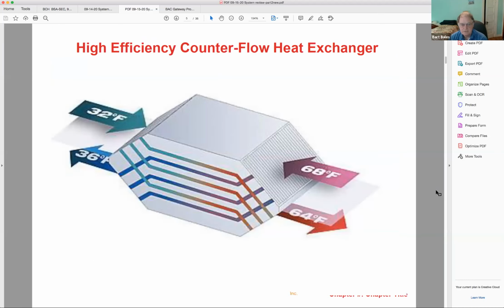Next slide. The most effective kind of heat exchanger is counterflow, where things run opposite to each other. Counterflow heat exchangers can get on the order of 85 to 90% efficiency, which has some very useful impacts. You can see that the temperature difference between the temperature going out of a space and coming into the space is only 4 degrees there. It's 68 going out and 64 coming in. So it's not going to chill the space much, and you may be able to deliver it without tempering if you deliver it in the right location.